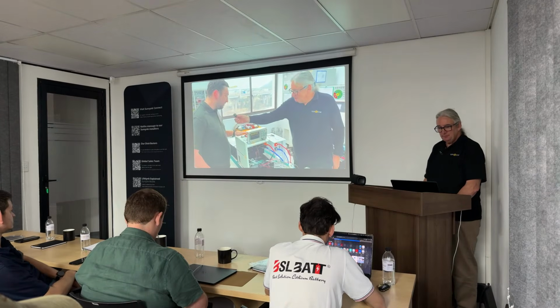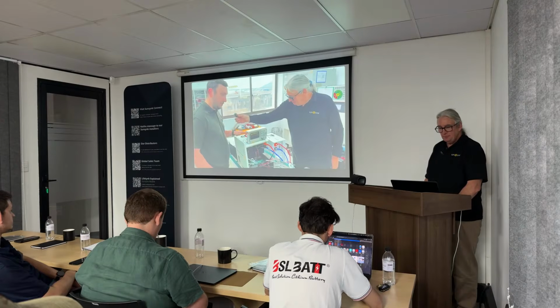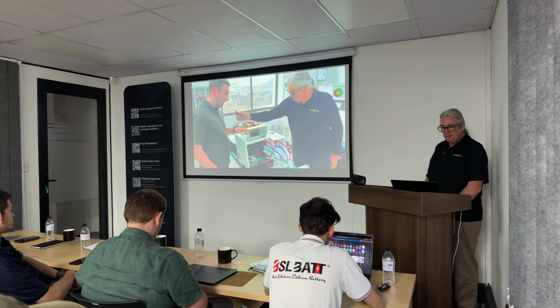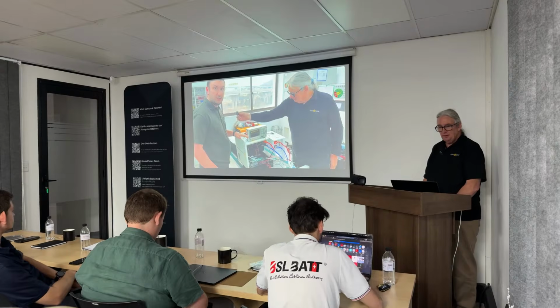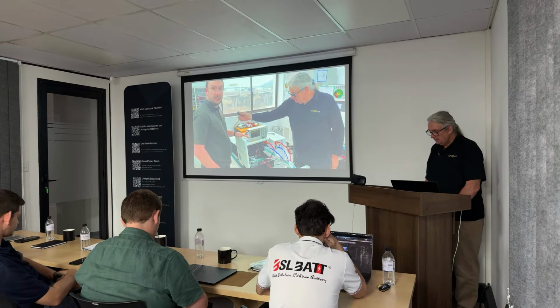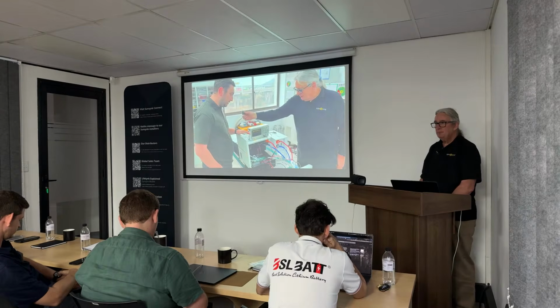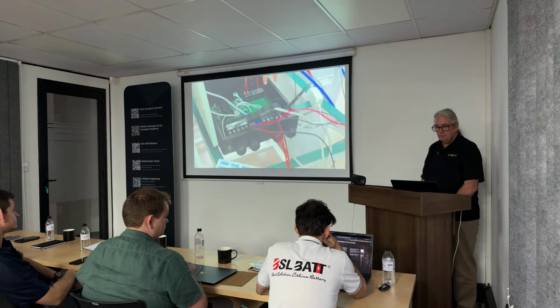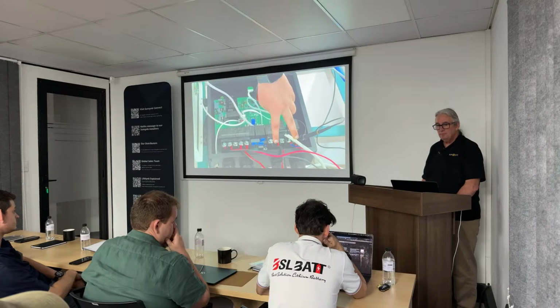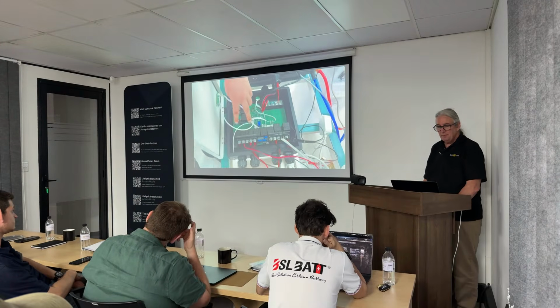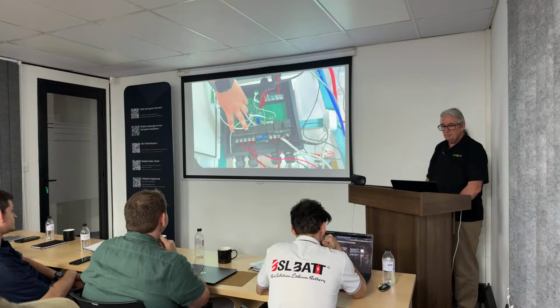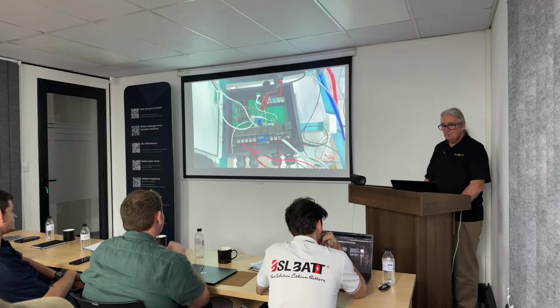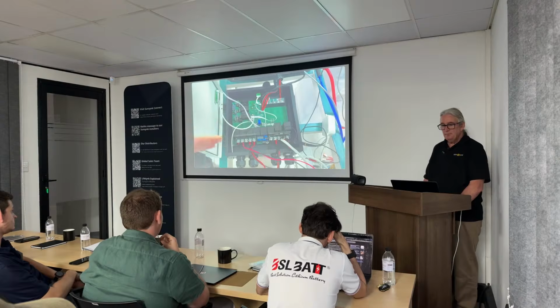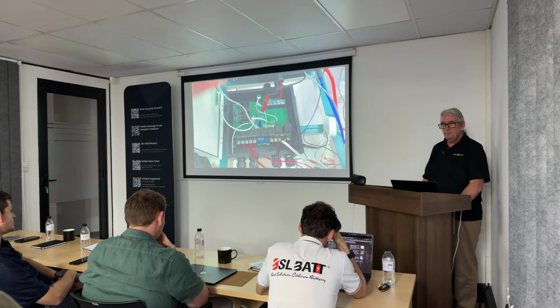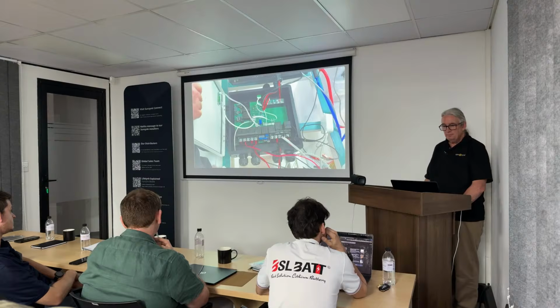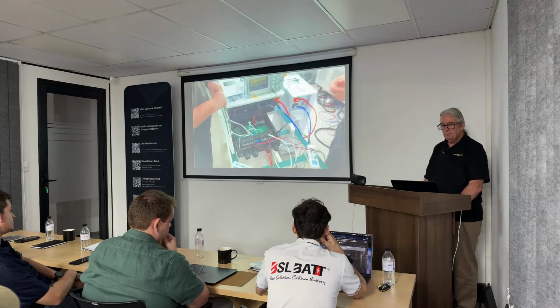On the Hyper Gateway, we've pretty much designed this to allow whole home backup, where somebody can have their UPS loads and essential loads connected, but also have the non-essential loads connected when there's a power outage. By doing that, we've got a load 1 and load 2 terminal out here. We've also added the nice feature of a gen and grid connection in, so people can connect both systems to the Hyper Gateway, and you can control either the generator or the grid to be on. So you've got every connection you'll ever need.